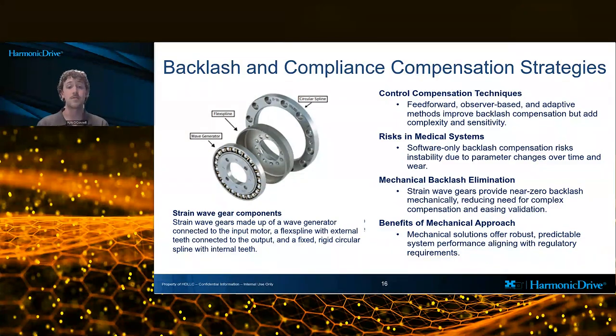In medical systems, where validation and long-term stability are important, reliance on software-only compensation can be risky. Changes in backlash due to wear or temperature can invalidate compensation models, leading to worse performance or instability. Or if you're using adaptive control, that's just much more complicated overall. So it's better to avoid it.